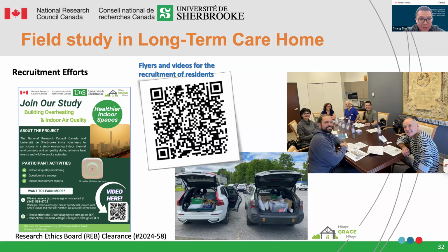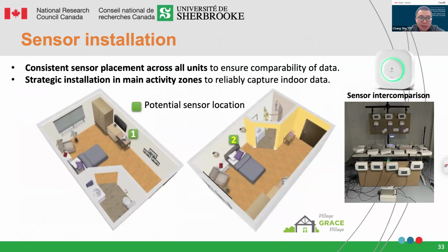So next slide, please. For the sensor installation, we have done a thorough preparation for all the sensors. We need to make sure all the readings are comparable. So before the installation, we do a sensor intercomparison in a well-controlled chamber, measuring particles and temperature to make sure all the readings are consistent. And for the installation on site in each unit, we discussed a lot with the local building manager about the detailed sensor location.